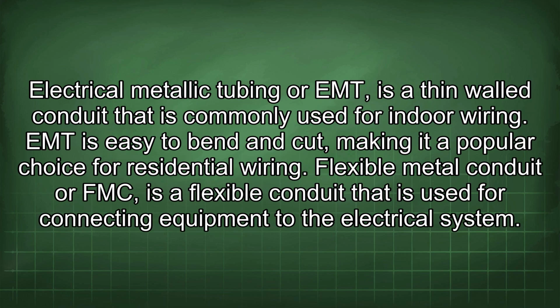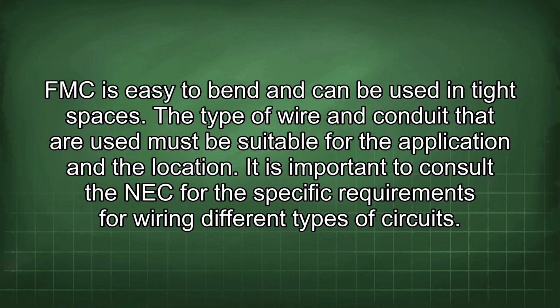Electrical metallic tubing, or EMT, is a thin-walled conduit that is commonly used for indoor wiring. EMT is easy to bend and cut, making it a popular choice for residential wiring. Flexible metal conduit, or FMC, is a flexible conduit that is used for connecting equipment to the electrical system. FMC is easy to bend and can be used in tight spaces. The type of wire and conduit that are used must be suitable for the application and the location. It is important to consult the NEC for the specific requirements for wiring different types of circuits.